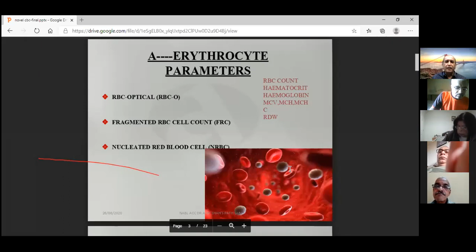RBC optical. When we are doing the RBC count, the previous method was conductivity, impedance. But in newer analyzers, with newer technology, RBC optical gives a very accurate RBC count. This is a little bit of technology, so I will just brush over it very fast. Especially in severe microcytic hypochromic anemia, where the RBCs are fragmented and small, sometimes the analyzer will miss their count, so we get a falsely low RBC count. In such cases, with the optical method, fluorescent method or laser technology, each and every RBC is counted. So you'll get a corrected RBC count even in severe microcytic hypochromic anemia.